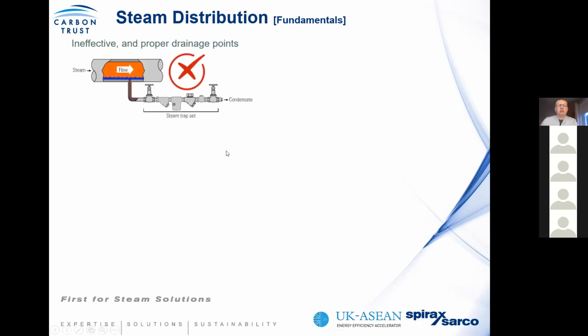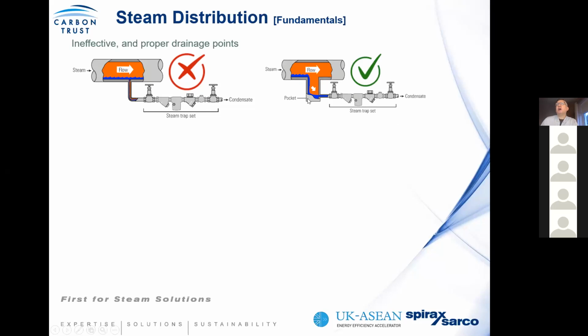So when you start looking at trapping, the function of distribution trapping is to remove these condensates which are generated by the distribution process itself. However, in this scenario, please remember, you have a flow of steam at velocity through a pipe. So we're seeing plenty of cases where you have a small tapping like this into a trap. Although it will remove condensate, it won't remove all the condensate because condensate will be pushed past the trapping point or tapping purely because of the velocity of steam. This is the best in class, where you would install what we call a full-size dirt pocket, where the condensate under gravity would fall into this dirt pocket and be removed by the trap, such that you don't carry on water or condensates to the end user or the next part of the distribution system.